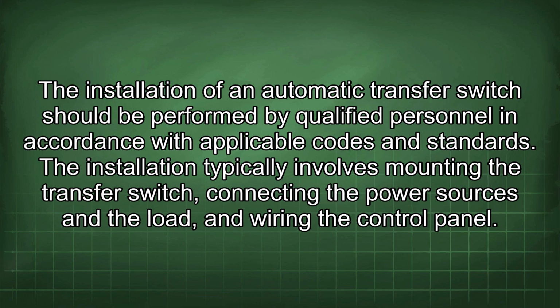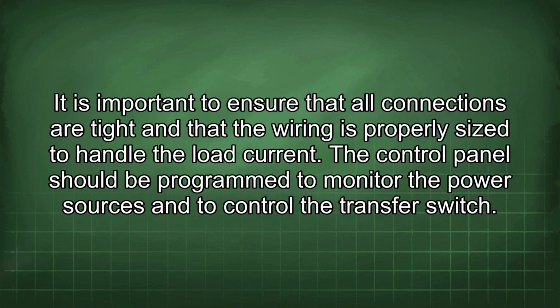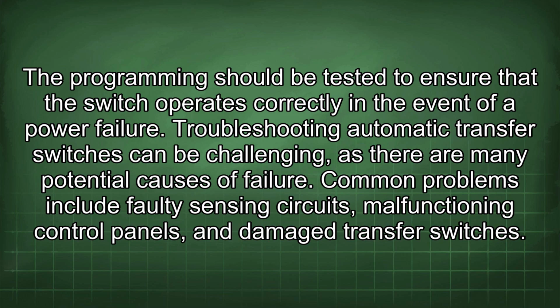The installation of an automatic transfer switch should be performed by qualified personnel in accordance with applicable codes and standards. The installation typically involves mounting the transfer switch, connecting the power sources and the load, and wiring the control panel. It is important to ensure that all connections are tight and that the wiring is properly sized to handle the load current. The control panel should be programmed to monitor the power sources and to control the transfer switch. The programming should be tested to ensure that the switch operates correctly in the event of a power failure.